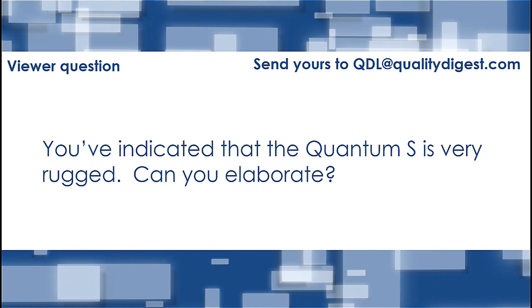Okay. You've indicated that the Quantum S is very rugged. Can you elaborate on that? Yeah, before we ship out every arm, it goes through a series of ruggedness tests. We do temperature cycling from -5 degrees Fahrenheit all the way up to 140, which should cover the vast majority of operating temperatures, I imagine. We also do a vibration shake test. We just shake the arm for a while, make it dance. Then we do a drop test. We drop it at least 4 times in the case, and then we do a recalibration and make sure it's measuring within standard after all those tests. So this has been battle tested and proven to withstand anything you're going to throw at it.